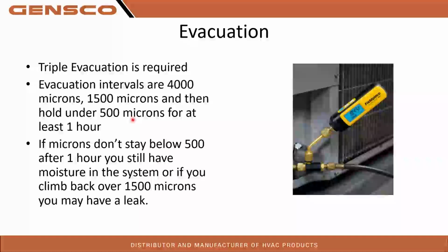So this is a very important step. As I'm sure most of you know, if you don't get a good vacuum on your system, any moisture will mix with your oil inside that equipment and the compressor, and eventually ends up turning to acid and leads to compressor failures. So we don't want you to do that. We don't want to see you do that. Replacing compressors, as a few of you are probably well aware, is not the easiest thing to do on the Mitsubishi systems. You have to pretty much take the whole unit apart in order to do it.